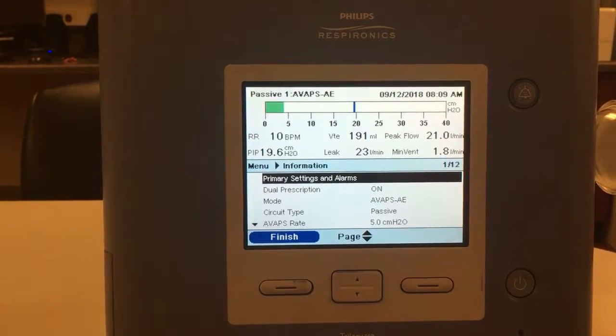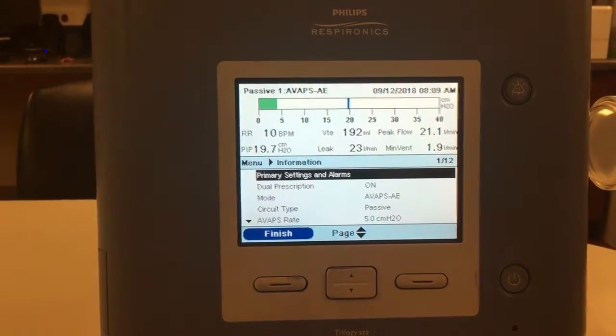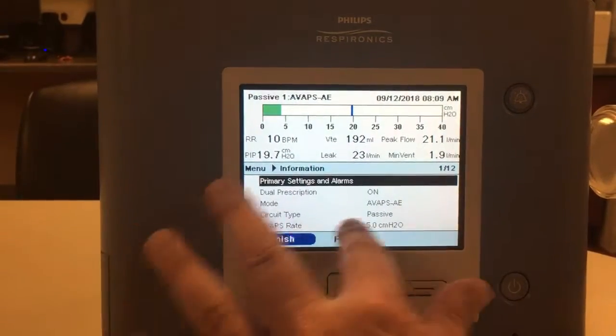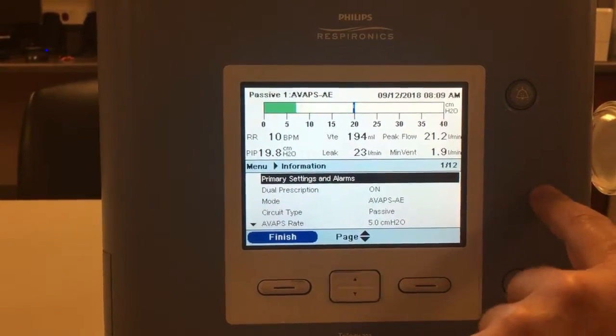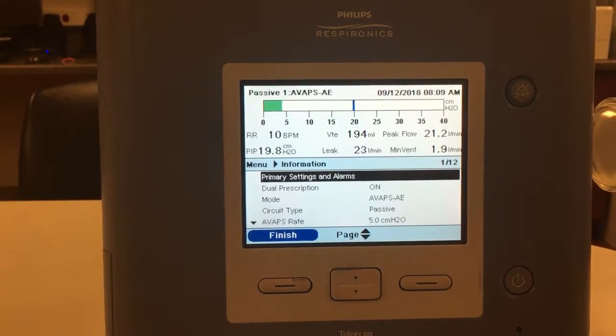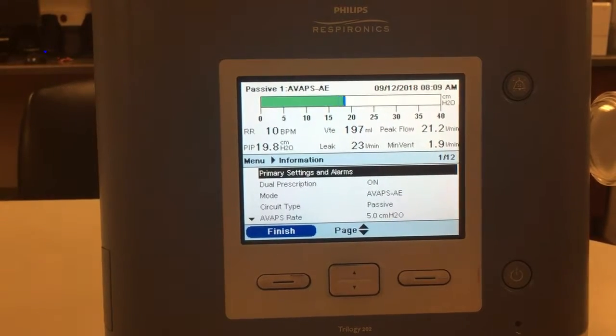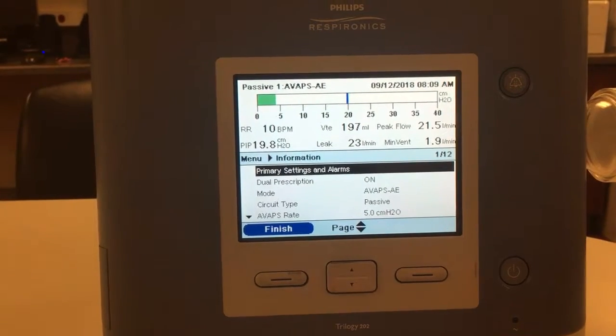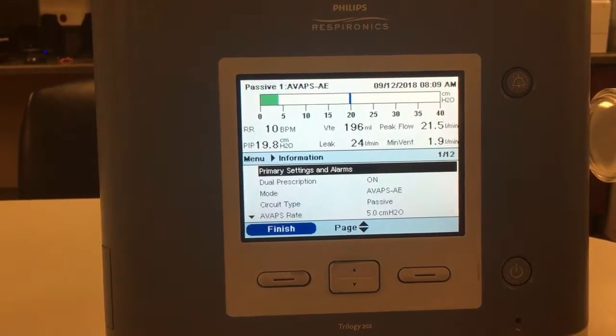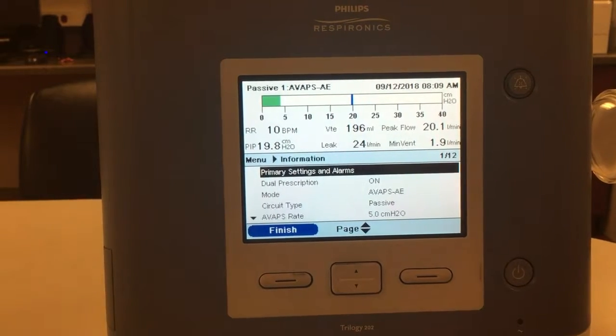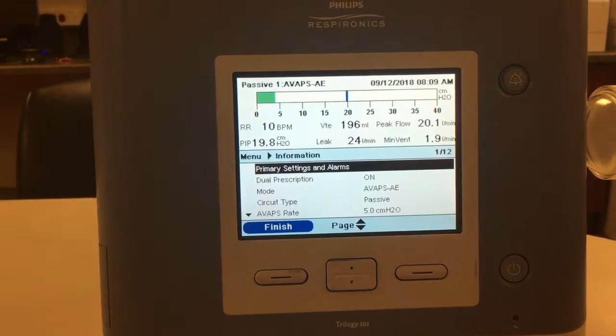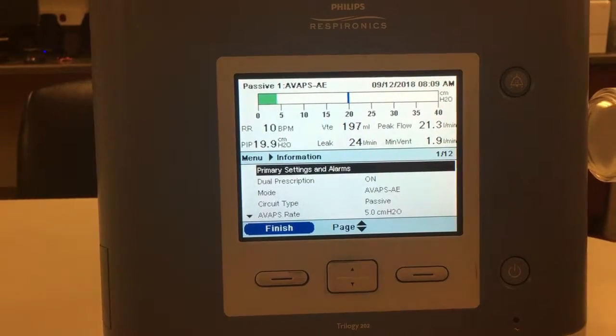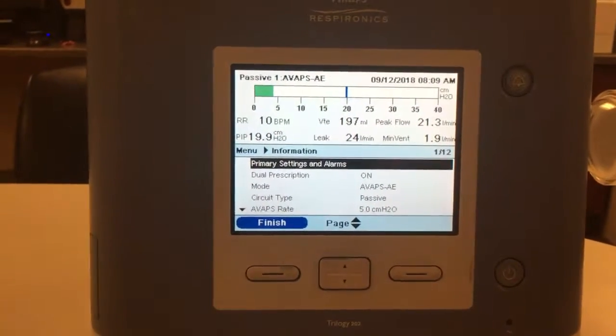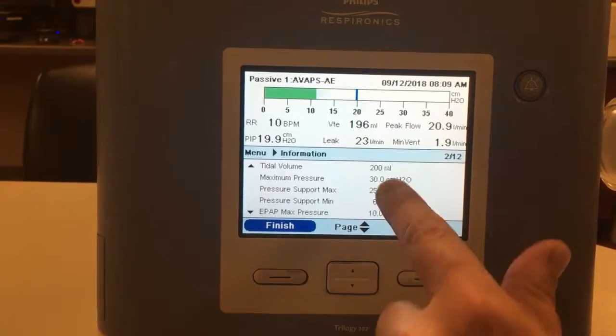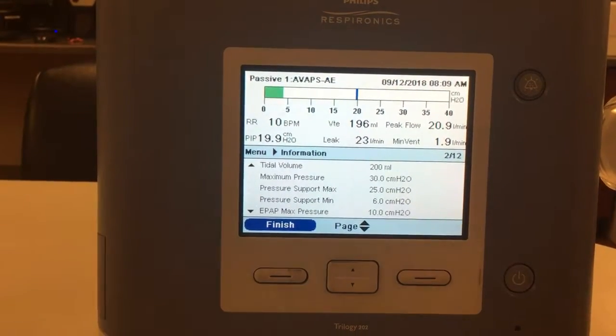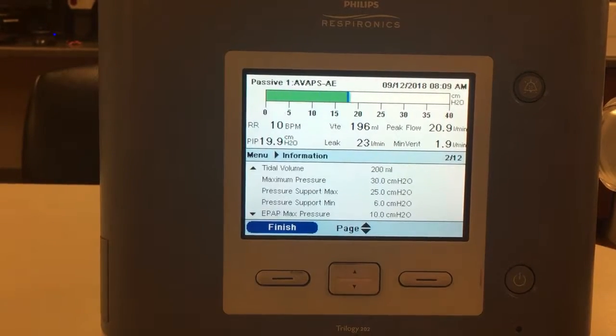So what that means is this is a setting that can go anywhere from 1 to 5. And what this will dictate, from 1 being an AVAPS AE rate, is how quickly the ventilator will make adjustments to maintain the tidal volume set. So an AVAPS rate of 1 will be very slow adjustments. An AVAPS rate of 5 will be much quicker adjustments.